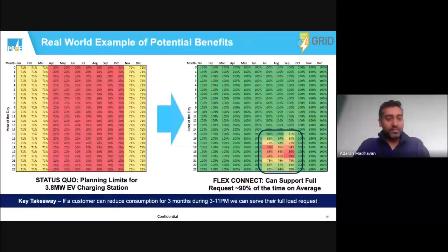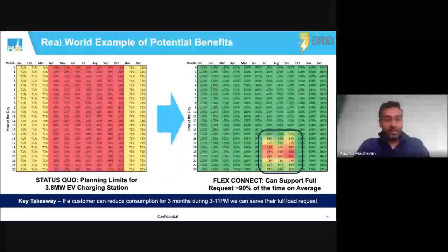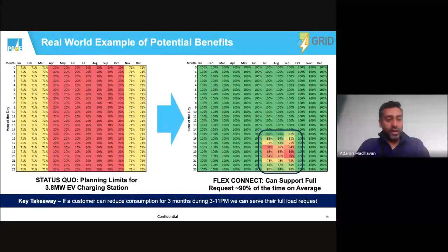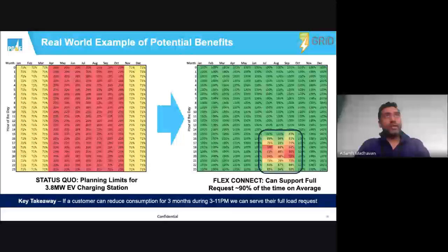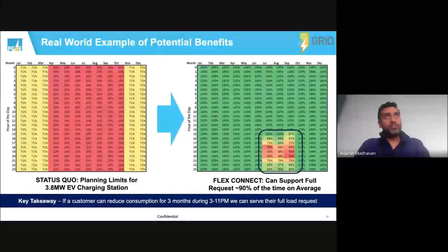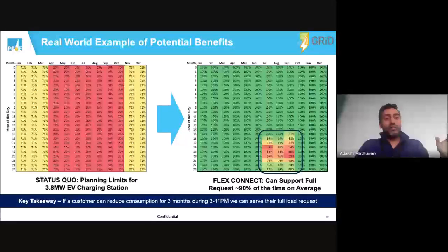This is an example of a 3.8 megawatt EV charging station that applied to connect. It's an actual example, and the site is actually live right now. On the left-hand side, you can see the static planning limits, like the static limits we were able to do using the planning process, which restricts the site to 71% in the winter months and 20% in the summer months.